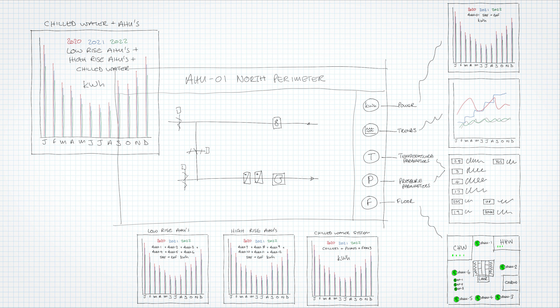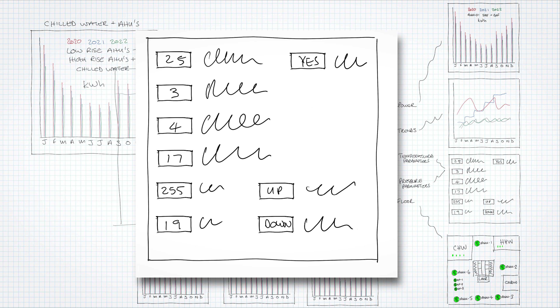Also on that right-hand side banner I have buttons for temperature parameters and pressure parameters. In the pressure parameters page, all the parameters you need to adjust as part of tuning the AHU supply air pressure reset strategy appear - and the same for temperature. If you're doing trim and respond, you'll be adjusting flags: how many flags to reset up, how many to reset down, resetting down half a degree Celsius every 10 minutes, or resetting the pressure up 10 Pascals every 10 minutes. You can password-protect that page, but people must be able to view the parameters.